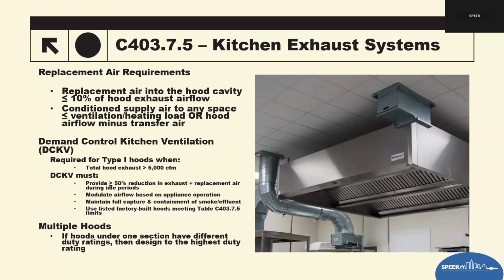So replacement air requirements. The code limits how much replacement air can be introduced directly into the hood's cavity. It cannot exceed 10% of the hood's exhaust rate, to ensure the hood is not flooded and remains effective. Conditioned supply air must also be limited, so it cannot exceed the larger of what is needed to meet heating and cooling loads, or the difference between hood exhaust and available transfer air from adjacent spaces. This is basically preventing oversupplying conditioned air just to feed the vent hood that's venting to the outside.